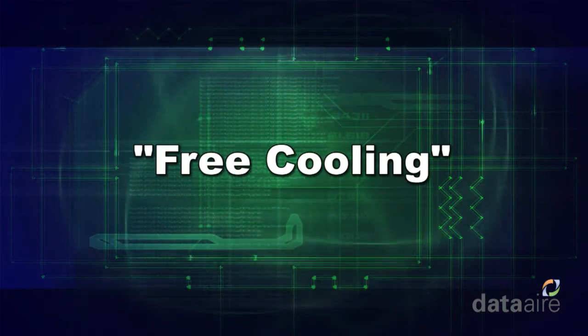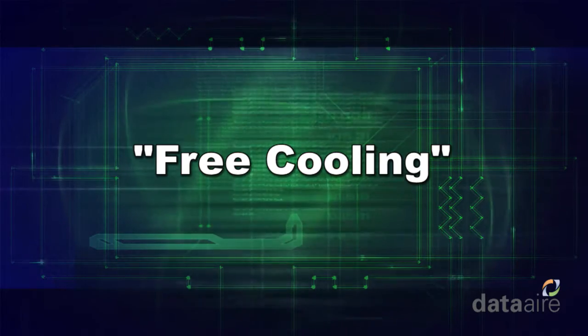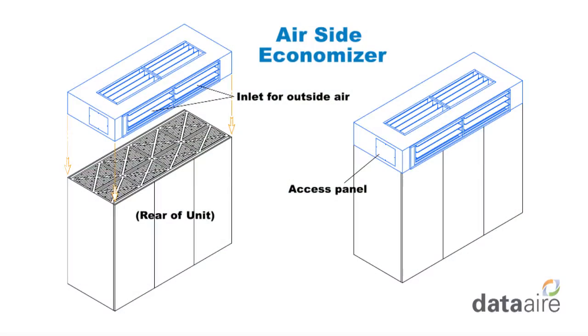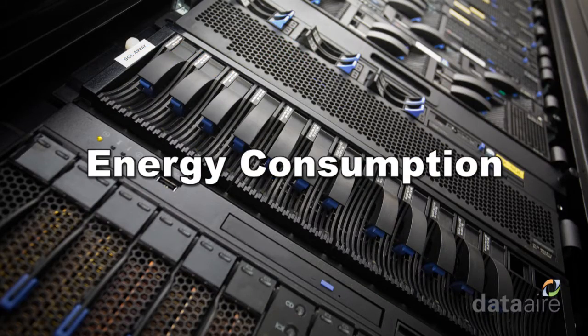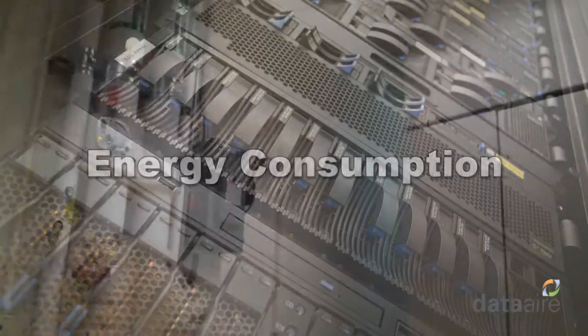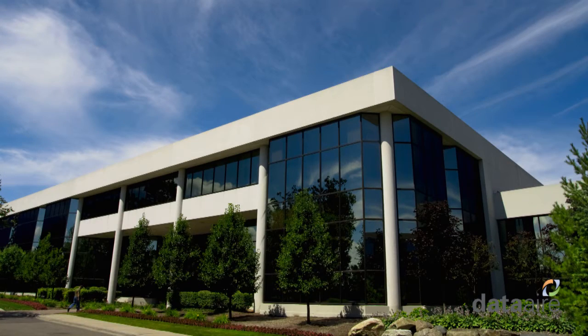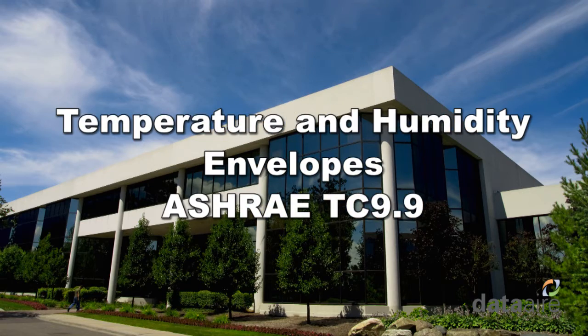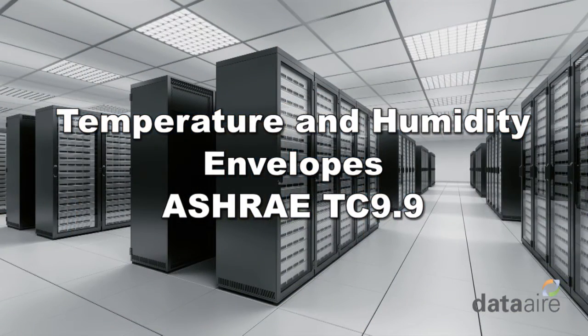Sometimes referred to as free cooling, Air Side Economizers have been around for some time, but it's only recently they've become popular with data center designers and managers. This is due to the increased attention given to energy consumption by data centers and the significant portion of that energy consumption attributable to cooling requirements. Another factor leading to the increased interest is the recent expansion of temperature and humidity envelopes published by ASHRAE's TC 9.9 Committee for Data Centers, which has made the use of economizers more economically feasible.